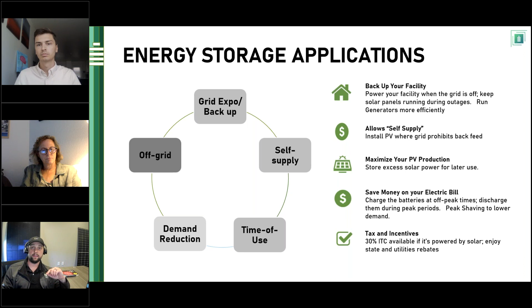You can use an energy storage system, essentially lithium batteries, to offset that peak demand and net it to zero. In my home specifically, I set up my system so that no matter what, my batteries are full and capable of offsetting my demand during our peak period, using absolutely zero energy during that time. This not only offsets the astronomical time of use rate but nets that demand charge to absolute zero, so it has no influence on our electric bill. That's an important consideration, since time of use and demand can go hand in hand with one another.